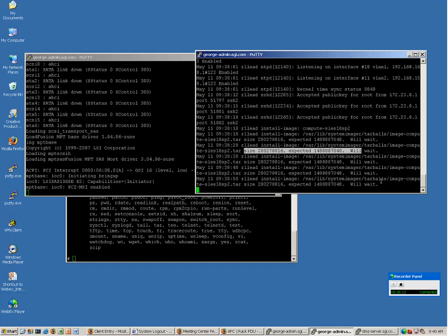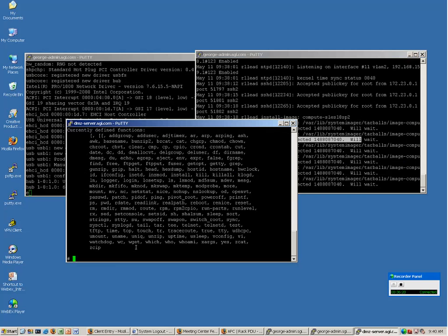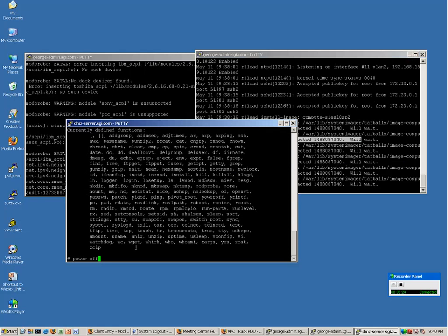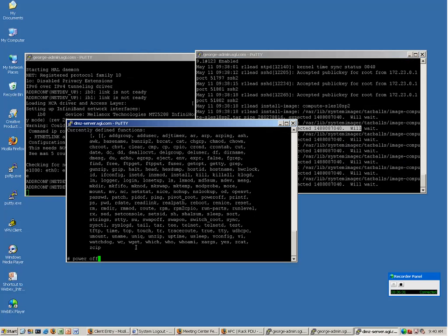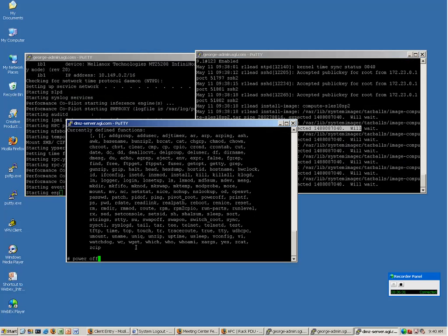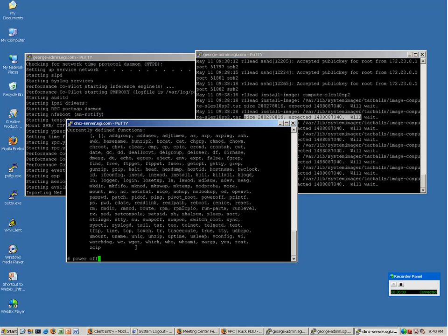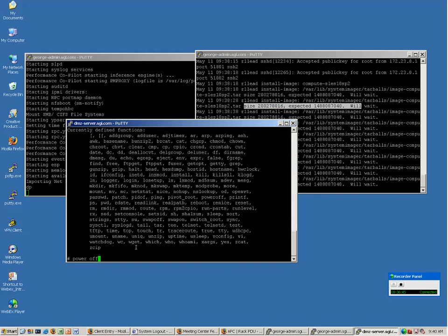We okay right now? Yeah. Also down here, there are a variety of things you can do, but basically what I did for Connie yesterday was a power space off and then a power space on. That does not shut down the BMC, or I'm sorry, the CMC. That shuts down the logic attached to the CMC. So if I do a power off, the IB switches, the Ethernet switches, and the logic to connect to the blades for their power, control, fan, and temperature, that logic is powered off and then powered back on with the power on command. That's how I reset it remotely.